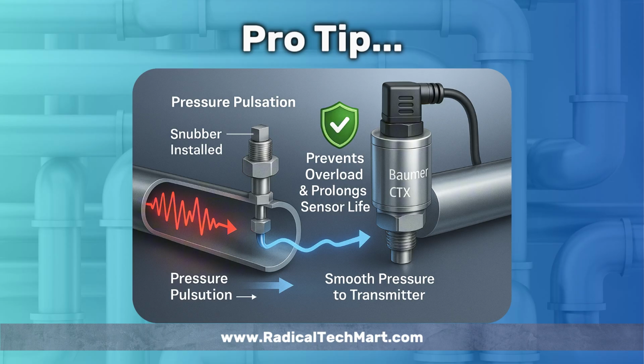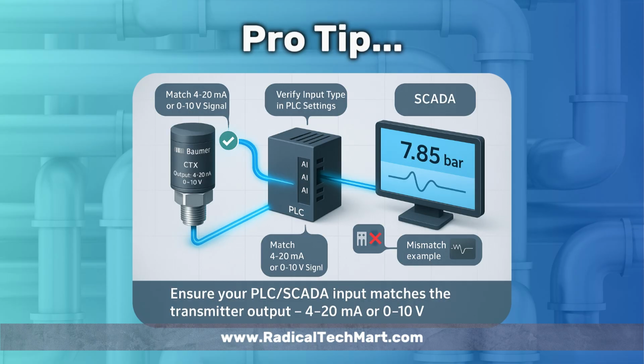Pro tip: if your system has pressure spikes or pulsation, add a snubber or damping orifice to protect the sensor. And for process monitoring through PLC or SCADA, always verify that your controller input supports the same signal type, 4 to 20 mA or 0 to 10 volt.